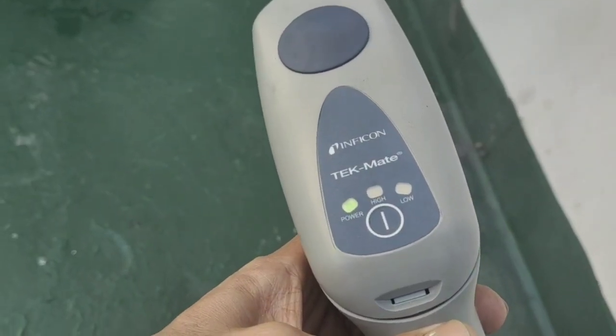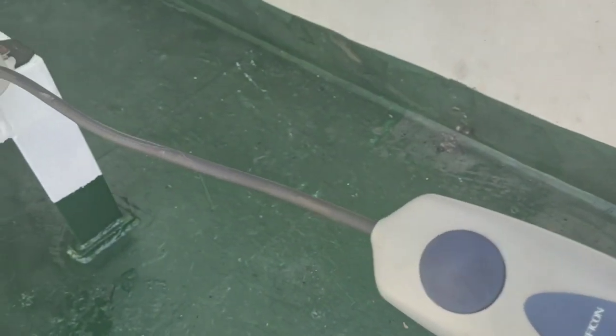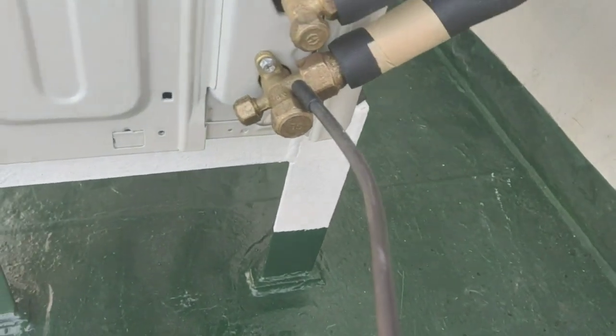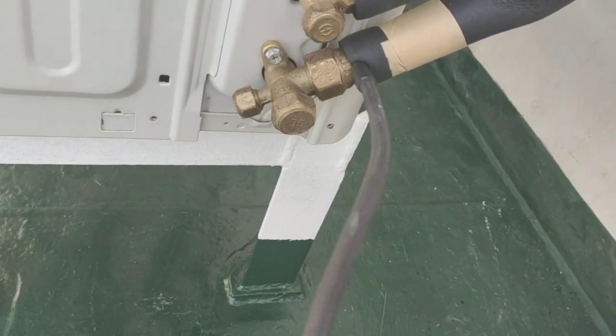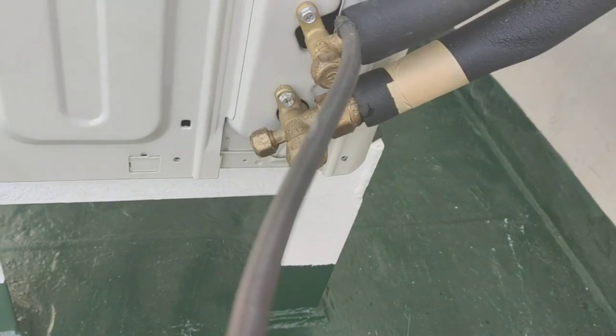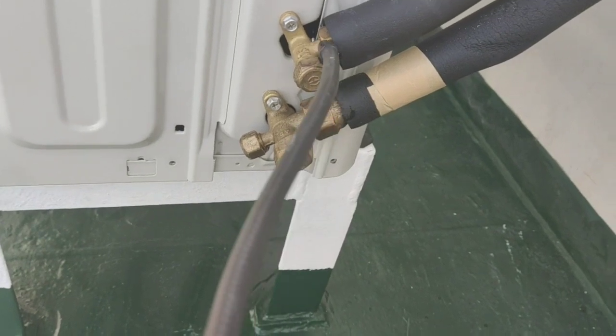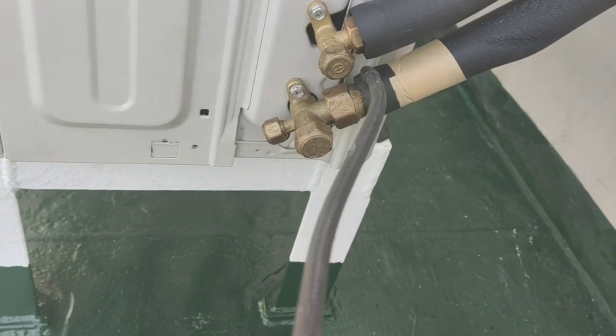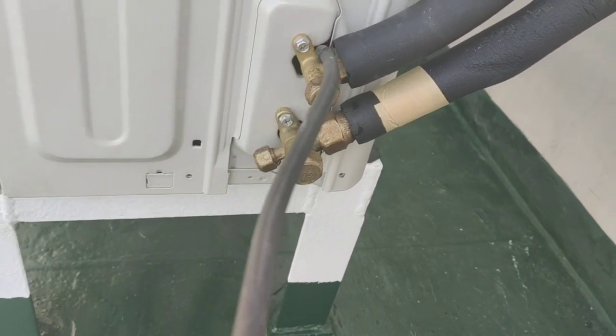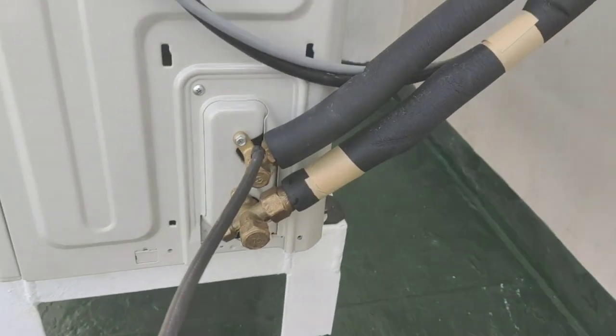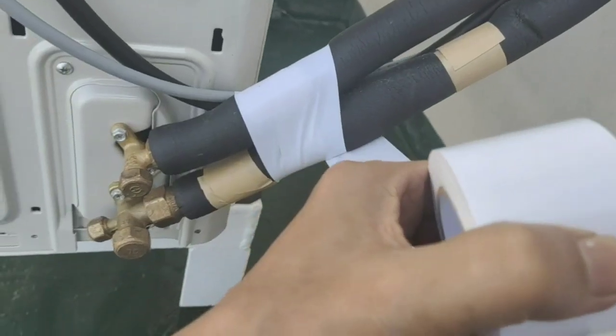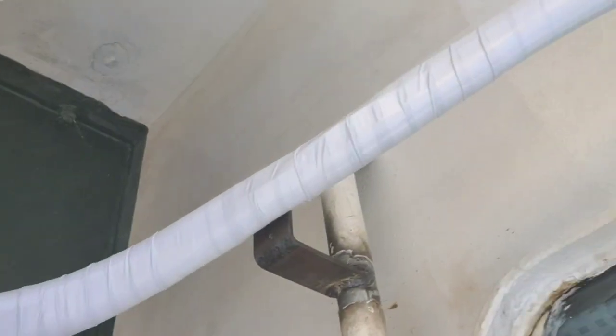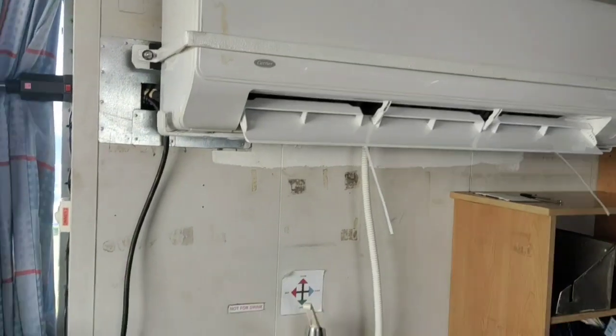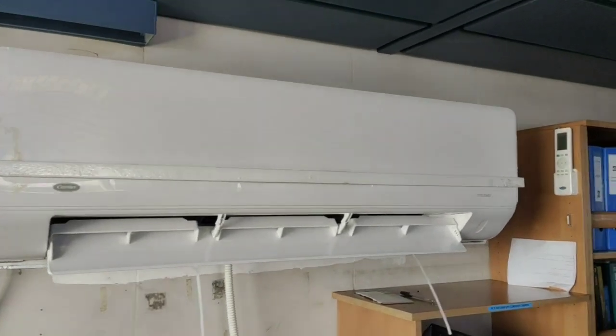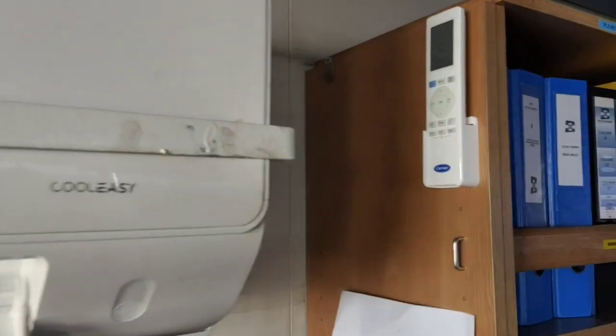Now we have already made the leak testing by all means before we connected all this. After connection of these pipes, we are double checking it with an electronic leak detector tester, and it seems that everything is fine. Actually at this point this aircon is already running, and I'm just rechecking the leak testing. Now I have to use the white tape to finish up the pipings and the cables, and inside also. As you can see, the evaporator side is already working fine.